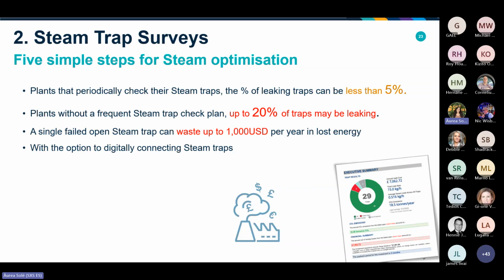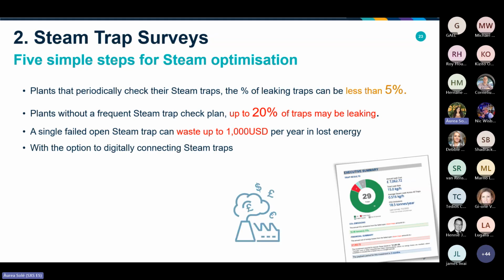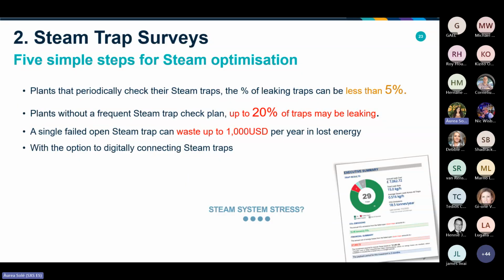For that, we offer a service which is a steam trap survey, where we do a health check of the steam trap population, and we provide a report with an executive summary of how the steam traps are working and which of them need to be replaced. On some occasions as well, we see that the model of the steam trap installed at the point of use is not the perfect one, and there are other models that could work better at that point. We also add suggestions for better-suited models at that point.